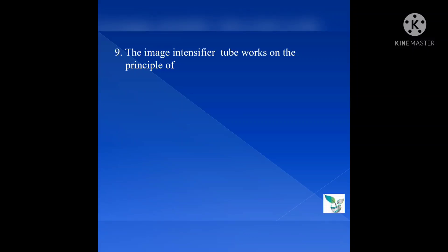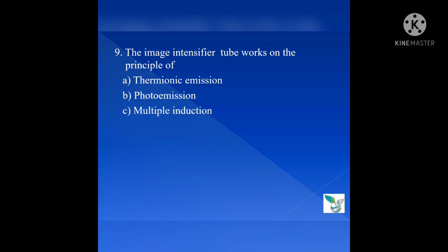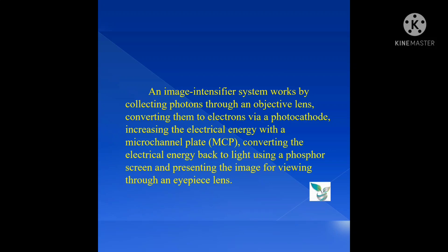Question number 9: The image intensifier tube works on the principle of — Option A: thermionic emission; Option B: photoemission; Option C: multiple induction; Option D: none of the above. The answer is Option B, photoemission. An image intensifier system works by collecting photons through an objective lens, converting them to electrons via a photocathode, increasing the electrical energy with a micro channel plate, converting the electrical energy back to light using a phosphor screen, and presenting the image for viewing through an eyepiece lens.